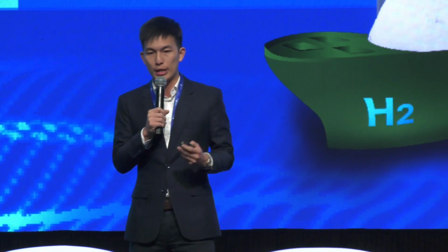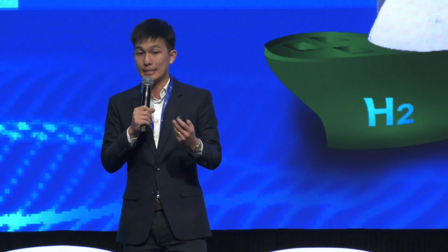In drafting the section on direct charging, TR25 was extensively referred to. Singapore's electricity regulations for electrical installations require a licensed electrical worker to ensure compliance with Singapore Standard 638, the code of practice for electrical installations. This covers the flow of electricity up to the connecting point. Specific requirements for the electric vehicle, charging system, and supply equipment regarding safety, communication, and hardware are adopted and adapted according to specifications defined in proven standards like MCS and CCS, and also as defined in this TR.